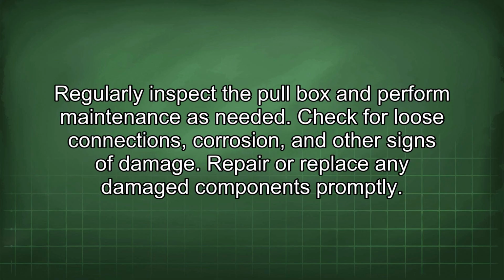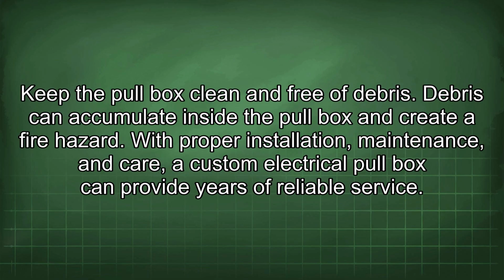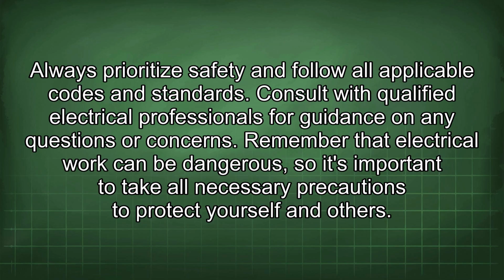Regularly inspect the pull box and perform maintenance as needed. Check for loose connections, corrosion, and other signs of damage. Repair or replace any damaged components promptly. Keep the pull box clean and free of debris. Debris can accumulate inside the pull box and create a fire hazard. With proper installation, maintenance, and care, a custom electrical pull box can provide years of reliable service. Always prioritize safety and follow all applicable codes and standards. Consult with qualified electrical professionals for guidance on any questions or concerns.